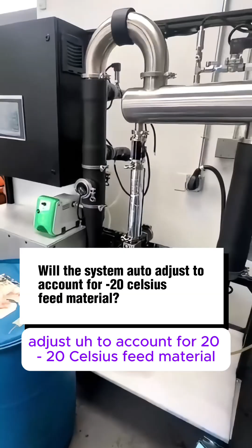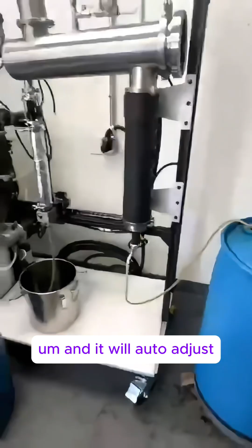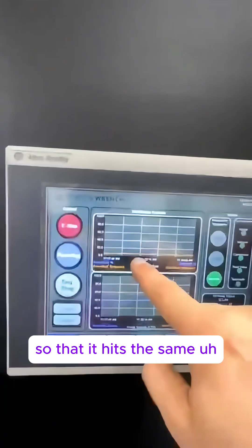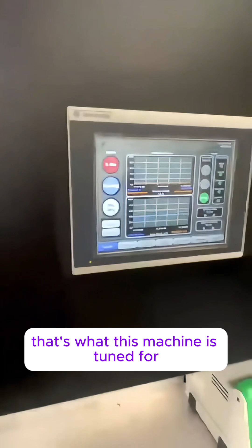The question was, will the system auto adjust to account for minus 20 Celsius feed material? Right now we're running room temperature, and it will auto adjust - it will run a little bit slower so that it hits the same residual solvent target in the oil. So you get the same oil quality coming out. That's what this machine is tuned for.